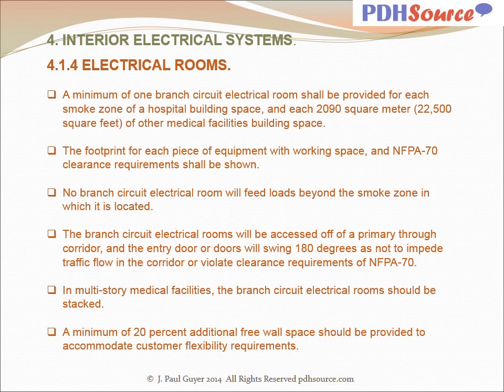A minimum of one branch circuit electrical room shall be provided for each smoke zone of a hospital building space, and each 2090 square meters or 22,500 square feet of other medical facilities building space. The footprint for each piece of equipment with working space and NFPA 70 clearance requirements shall be shown. No branch circuit electrical room will feed loads beyond the smoke zone in which it is located.